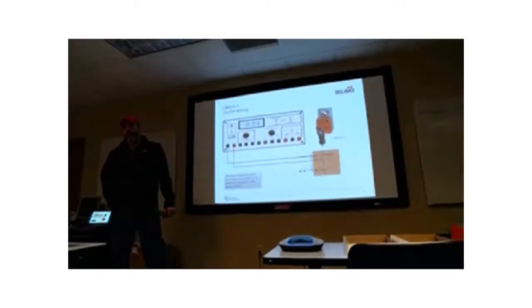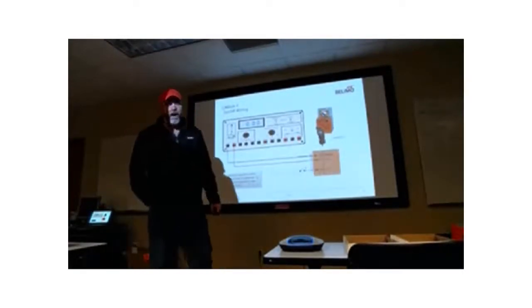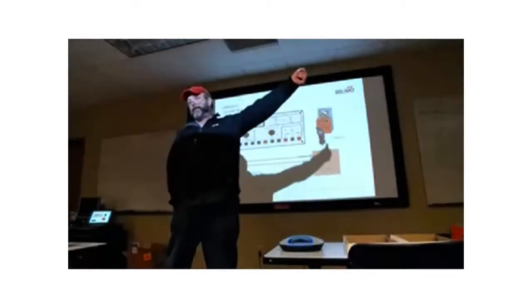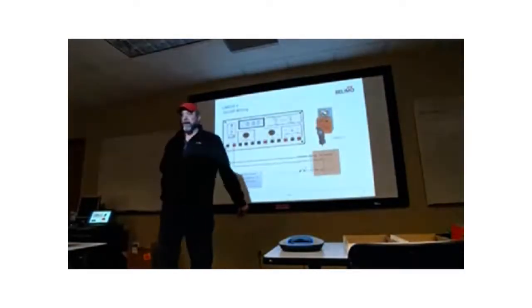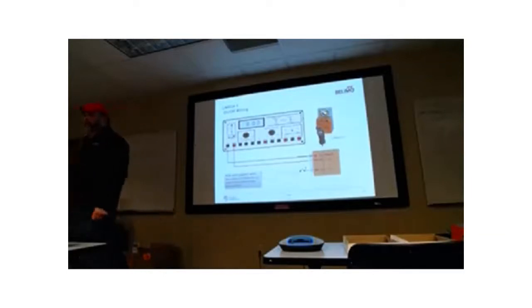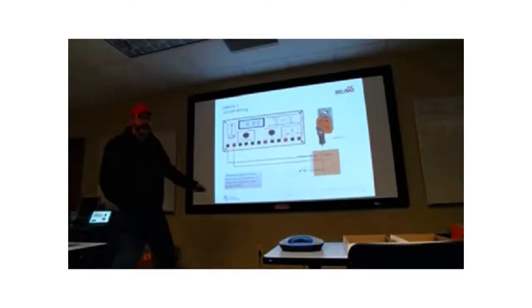So now we're going clockwise again. You can use your clutch to adjust the rotation if you get into the stops. Take the white wire and short it to the red wire at the terminal. Just go copper to copper, red to white. Leave it in the terminal block, but just go copper to copper with the red wire and see what happens. It should reverse rotation, right? It should reverse rotation. Okay, so here's what's going on there.